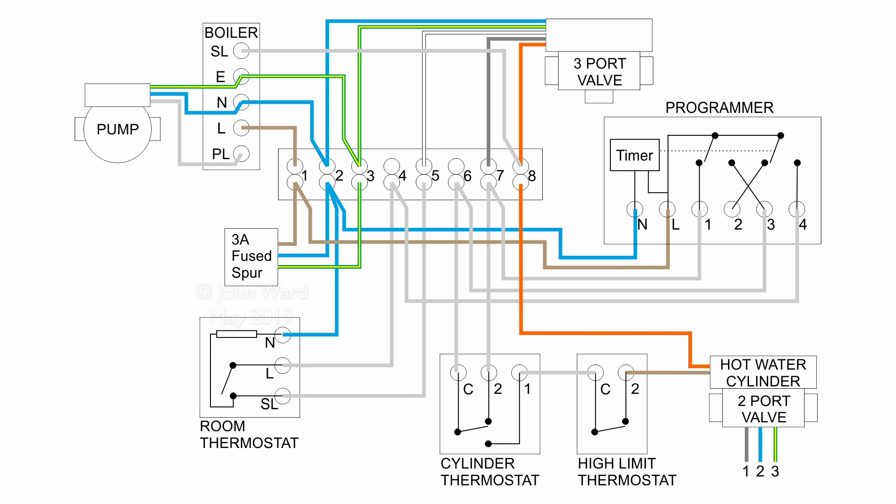So the method of operation in this case is fairly similar to what we had before, so power will come from the programmer there on terminal 3 with hot water on. They go through to terminal 6 there in the wiring centre, and just as before it goes to that cylinder thermostat. The difference here is that the output from the cylinder thermostat, which is pin 1 here, actually goes into the high limit thermostat. Now this is a normally closed thing, so in normal circumstances the power just goes straight through there and out on pin number 2.